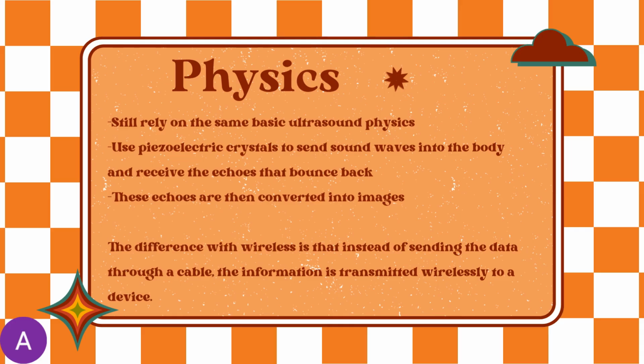The physics behind wireless ultrasound transducers is the same as a regular ultrasound probe. It still relies on piezoelectric crystals sending that sound, but instead of sending it through a cable to the machine, they send the information wirelessly. It's still the same basic ultrasound physics with echoes converting into images, but it's done wirelessly instead of through a cord, which is fascinating given how much technology has changed over the past few years.